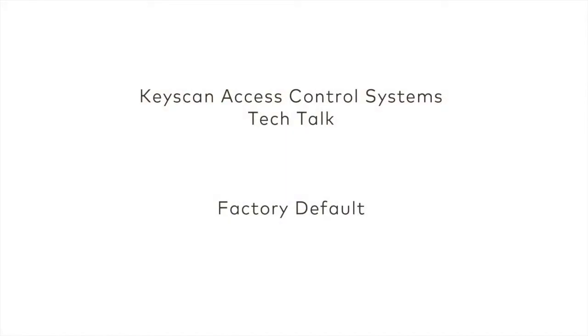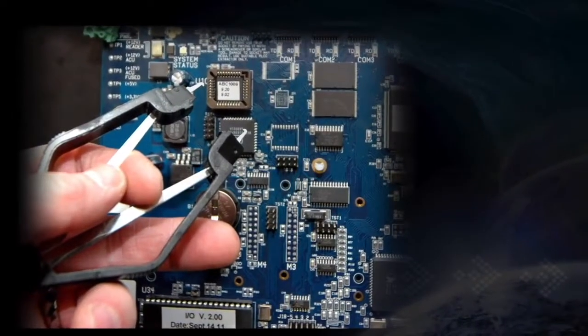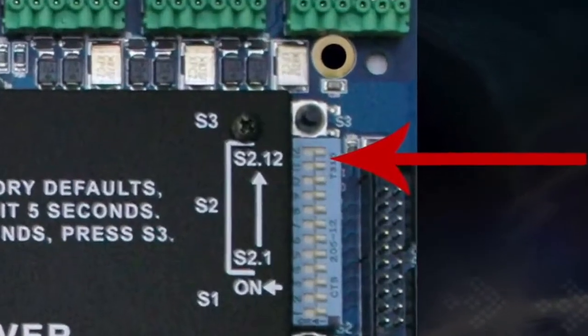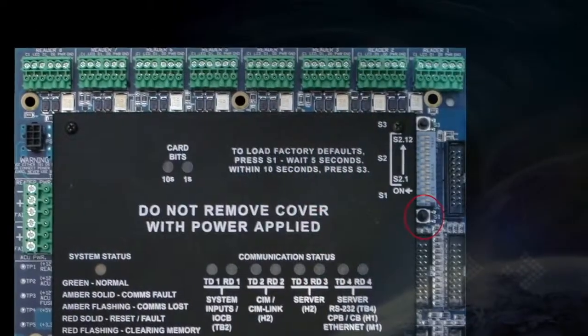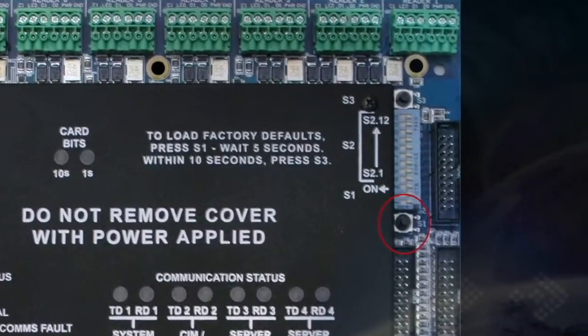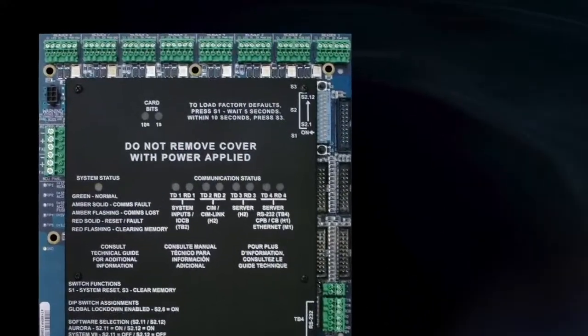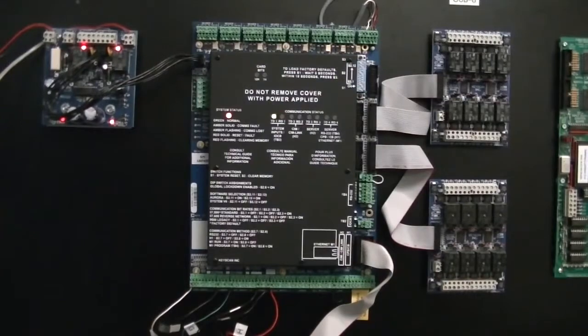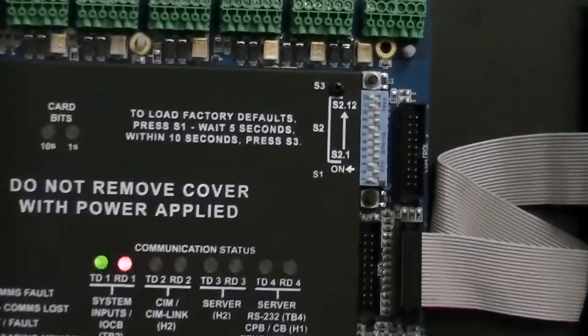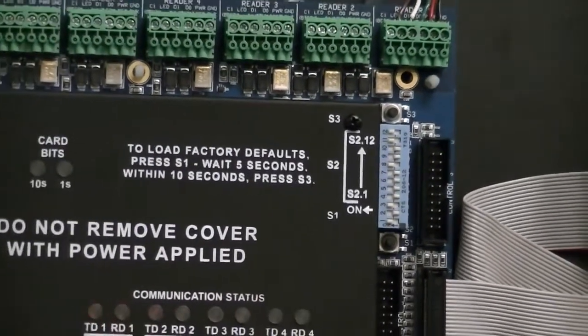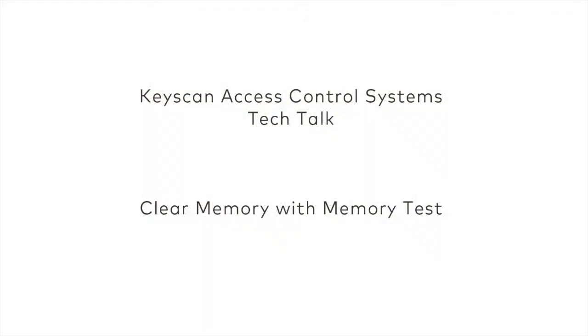In some cases, loading factory default settings may be required — any time an access control unit has been newly installed, a firmware chip has been changed, software selection switches have been changed, or if the protective cover has been removed to mount a NETCOM 2P directly on the unit. To do a factory default, press the S1 reset button momentarily, wait approximately 5 seconds, then press your S3 clear memory button. Once initiated, you'll hear an intermittent tone and the status LED will flash red. Once complete, the status LED will turn amber and the tone will stop. This process can take up to 2.5 minutes and is known as a clear memory with full memory test procedure.